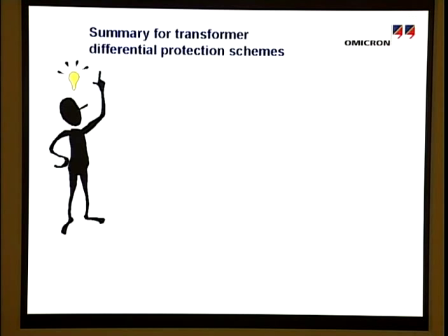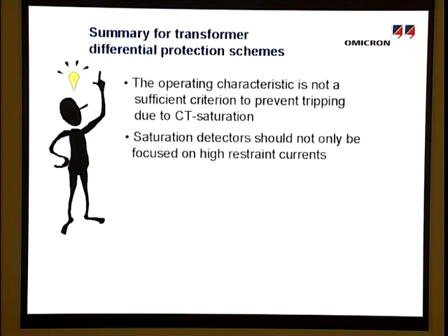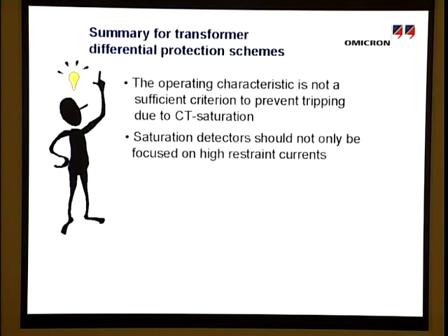As a conclusion, the following essential findings can be highlighted: The operating characteristic is not sufficient on its own to prevent tripping due to CT saturation. Saturation detectors should not only be focused on high-restraint currents. If the relay algorithm is based on the fundamental frequency of the differential current, applying TPX and TPZ cores at both ends does not create any difficulties and allows sensitive setting. Omicron provides solutions for analyzing and testing such complex situations.